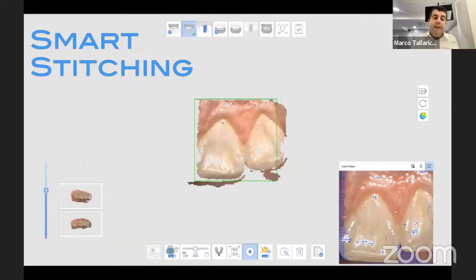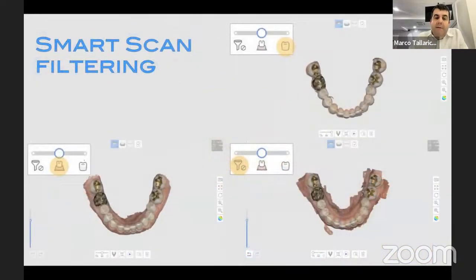Smart stitching, but my recommendation is a maximum of 2 different scans. Filtering options are no filter, teeth and gingiva, and only teeth. Here you can see different images. Usually I use teeth and gingiva. However, in the mandible, if you have a very complicated mandible, you can use just the teeth, particularly if the mandible is just...